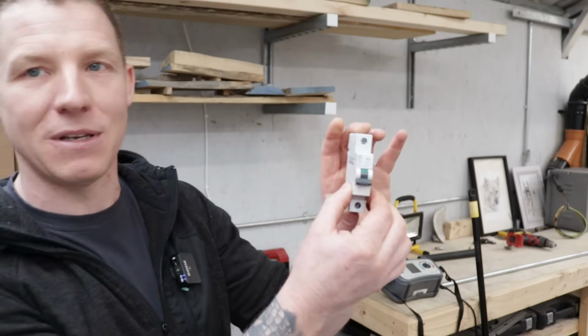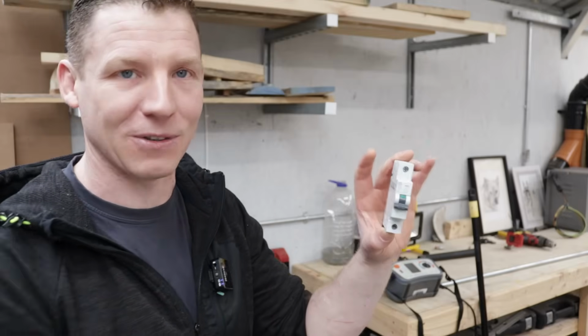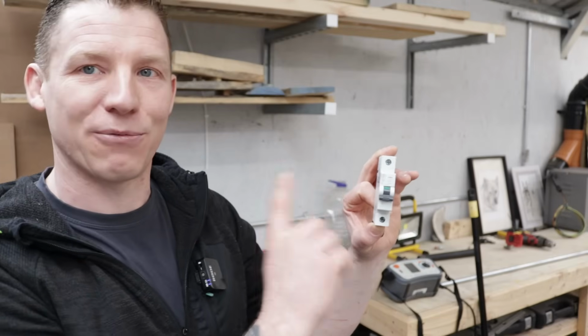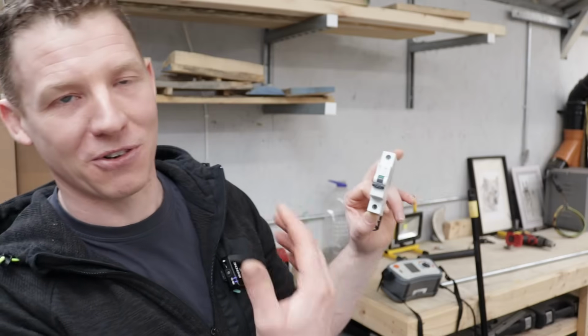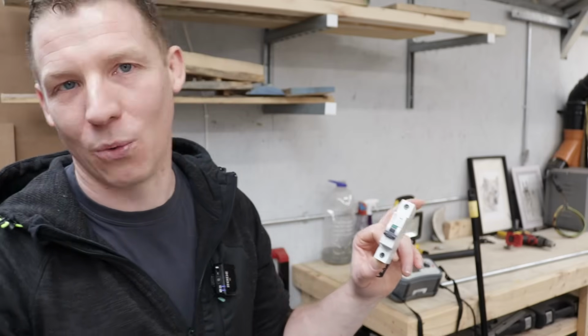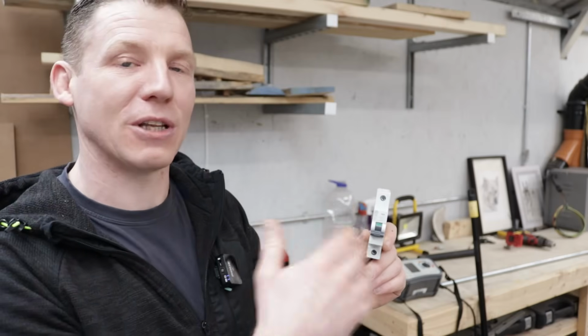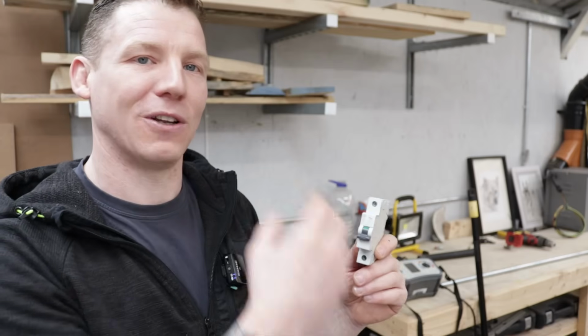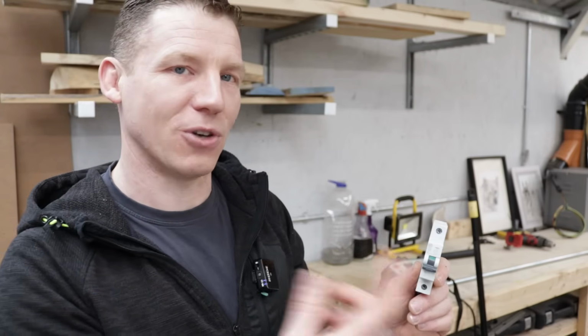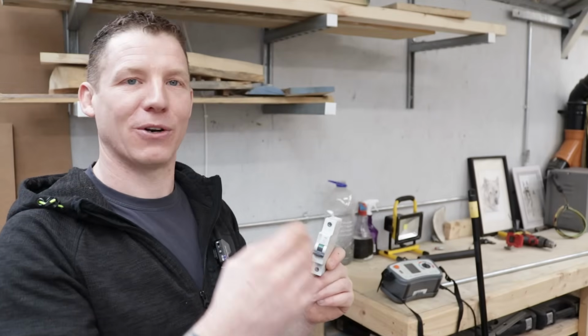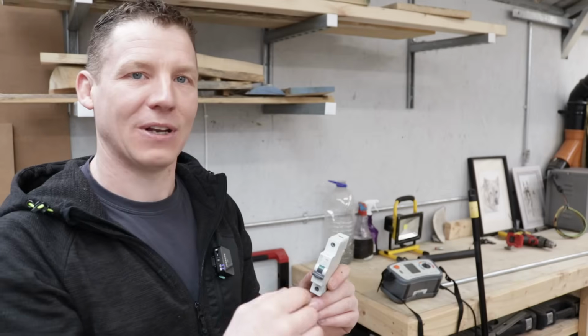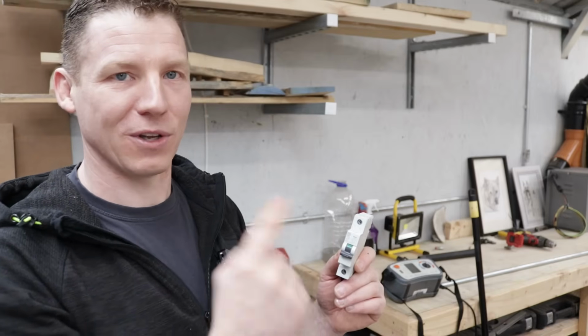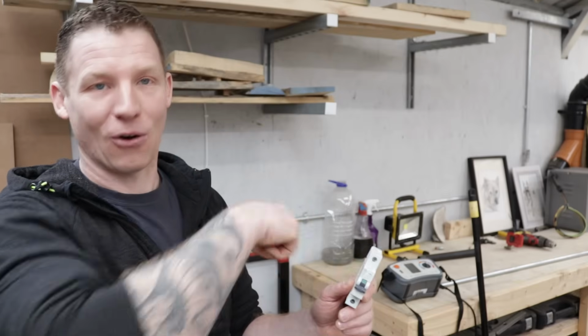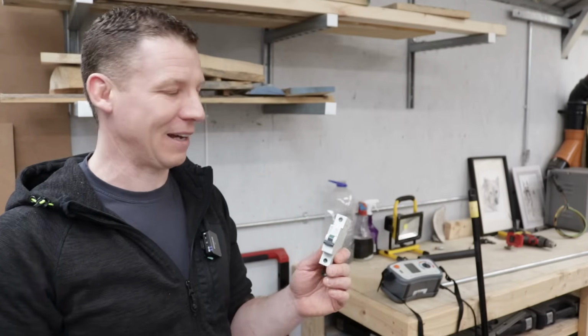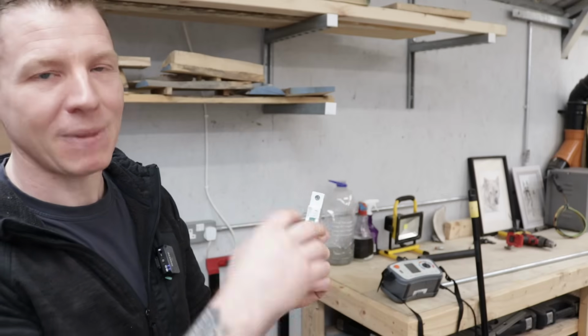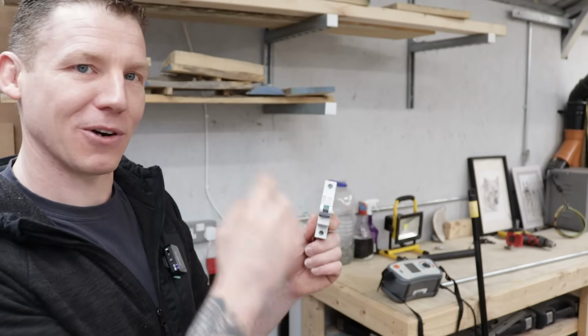So we have MCBs, miniature circuit breakers, trip switches, or breakers, whatever terminology you want to use. And these have a set fault current that's required to blow them out. Now these are B-type, which are domestic ones. You will use different notations depending on where you are in the world. But these require 3 to 5 times tripping or max load current in order to trip them out, and they're designed to blow out in 1/10 of a second on short circuit. So we have to ensure that the resistance of our circuit is low enough that we get on short circuit that 3 to 5 times current to blow this guy out. Because if we don't have that, this will not blow out quick enough. That whole circuit, like I said, will turn into a heating coil, and we really don't want that. So this is a 10 amp one, so that would need to be 30 to 50 amps we need to flow in an instant when we get a short circuit to blow this trip switch out.